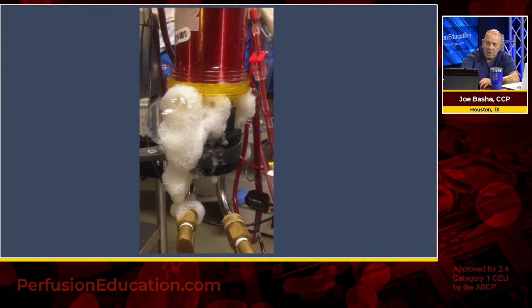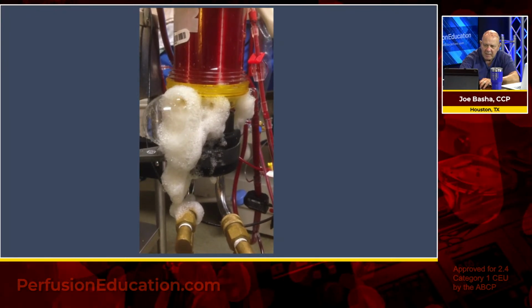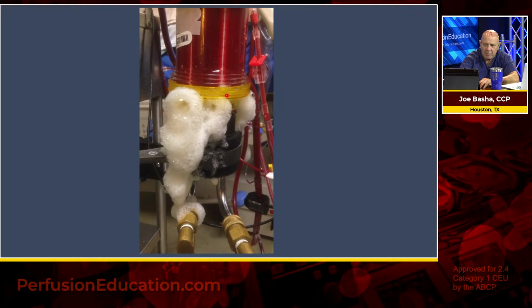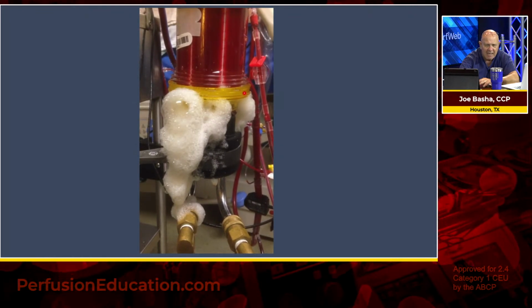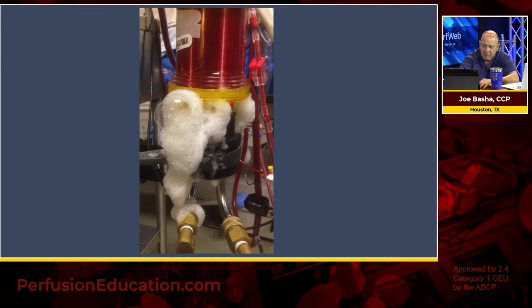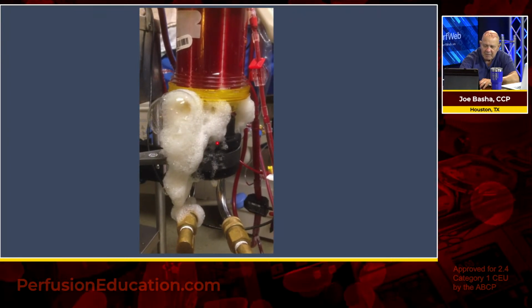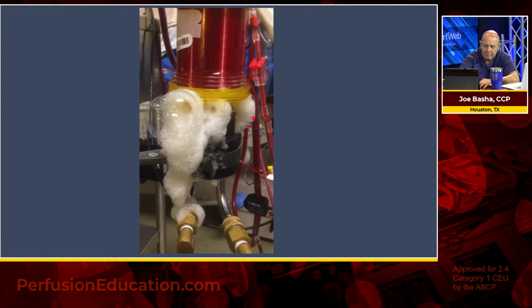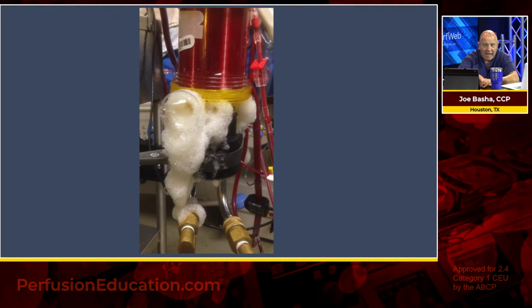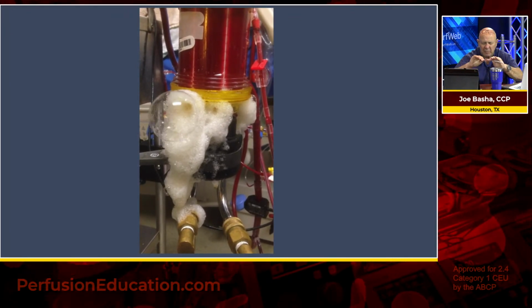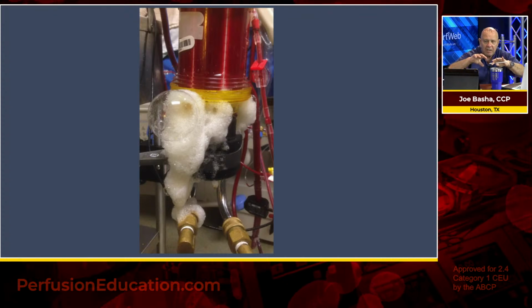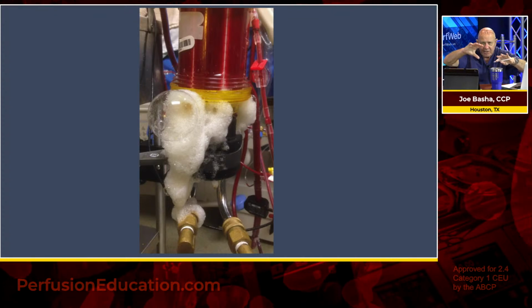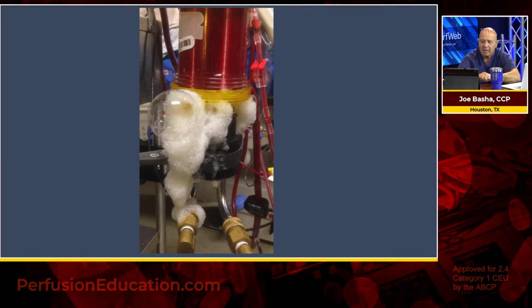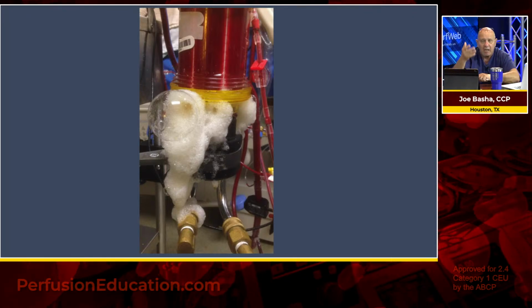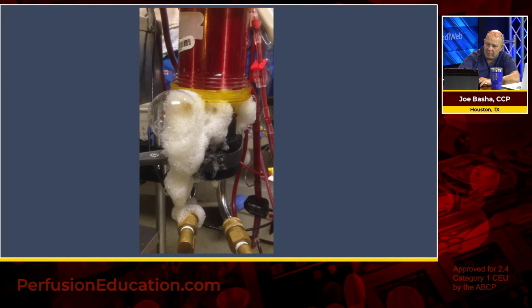But if you notice, you see the yellow ring I told you about? I know this is a polypropylene oxygenator, the same exact oxygenator as the one that I showed you, and this is what plasma leakage looks like. And that's caused either by the phospholipids creating that channel or by swelling the fibers, stretching and expanding the porosity of the microporous hollow fiber.